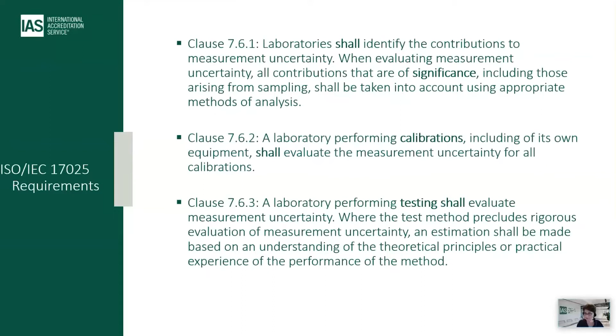That's what the standard says. So in note 3 of the standard, it references three items: the ISO IEC Guide 98-3, which is commonly known as the GUM, or the Guide to the Expression of Uncertainty in Measurement; ISO 21748, which is another ISO standard that has more of a top-down approach to measurement uncertainty; and the ISO 5725 series.